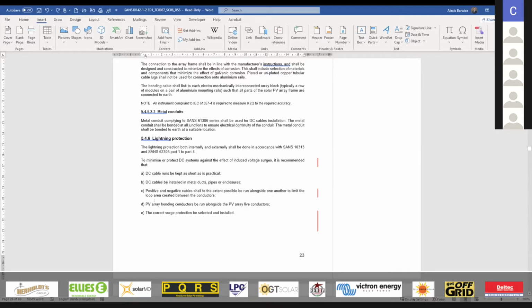The last 2 points are to do bonding conductors along the PV system. This is a very big topic we've had in the 10142, because it gets quite tricky when we do bonding from an electrical point of view. We are able to do bonding with, for example, a 2.5 mm² cable. Yet when we start doing purposeful bonding for lightning protection reasons, then we actually have to upgrade that to 6 mm² when we do not consider direct lightning strikes, and to 16 mm² when we consider direct lightning strikes. And I'll show you that in the 10313 standard in a few seconds.